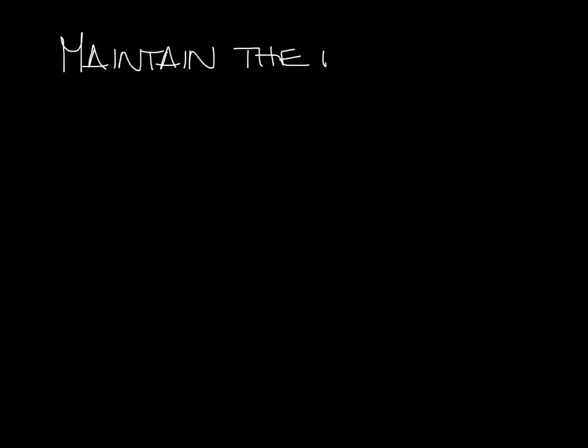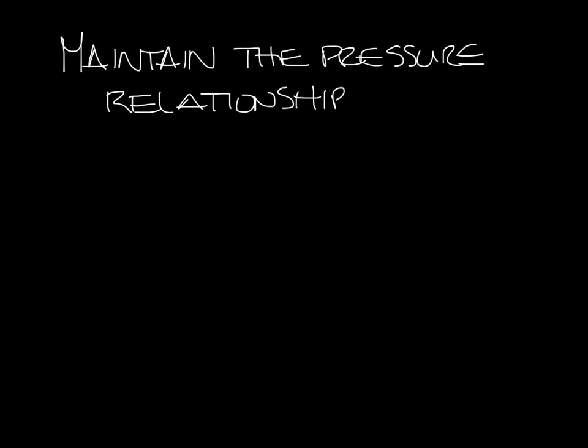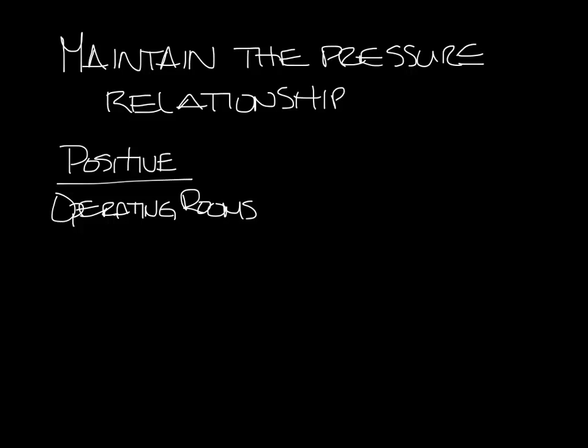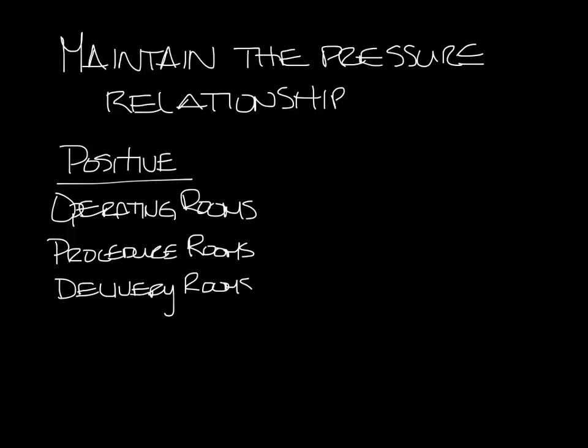The first sentence of the air distribution systems section, which is section 6.7, is: maintain the pressure relationships required in table 7.1 in all modes of HVAC operation. If you remember from the positive and negative pressurization podcast, you can use room pressurization to keep things in or out of a space. Some of the spaces that the standard shows as positive pressurization are operating rooms, procedure rooms, delivery rooms, and trauma rooms.